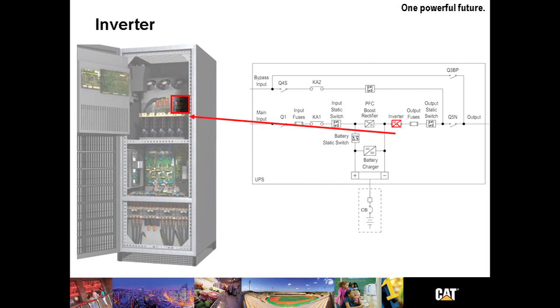Here we see the inverter section. The three-phase inverter with IGBTs, a non-isolated capacitive half-bridge. The term non-isolated refers to the fact that there is no isolation transformer, as in older topologies. The capacitive half-bridge, simply stated, means that the load is always powered by the DC bus and that the power is conducted through an inverter connected in a half-bridge configuration.